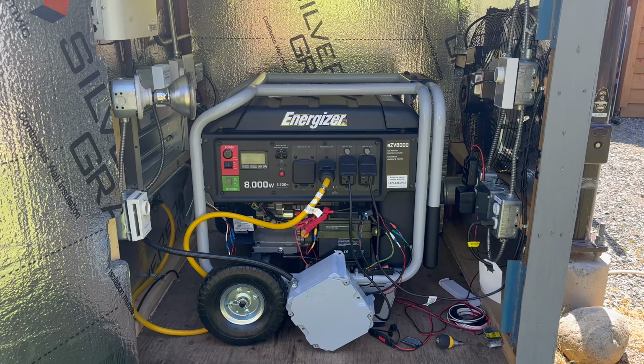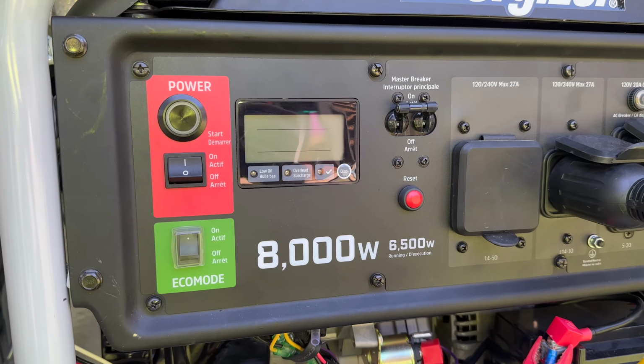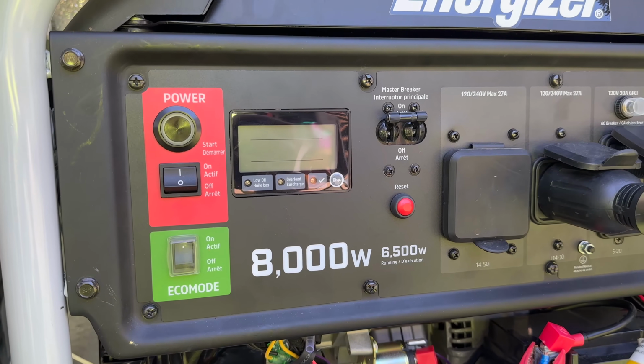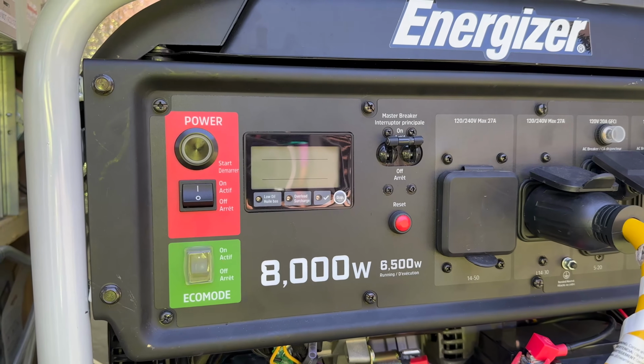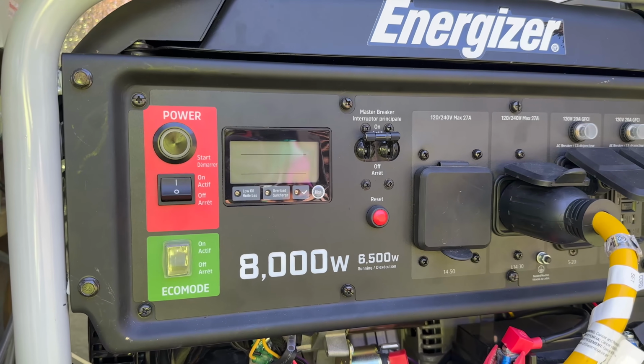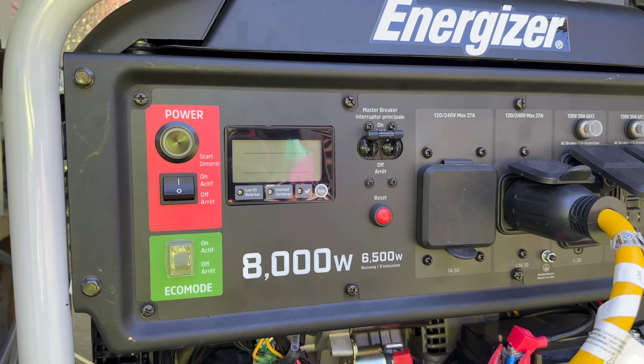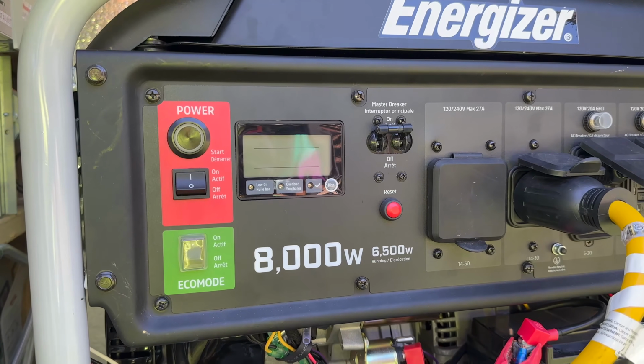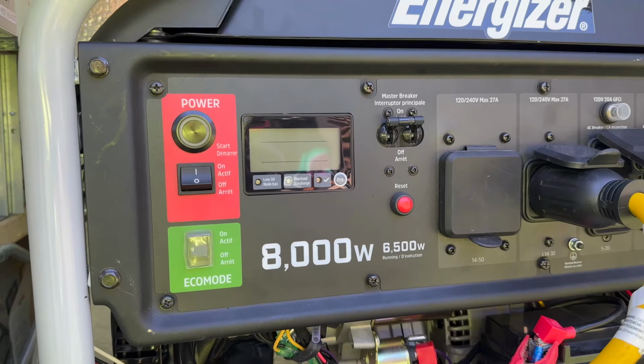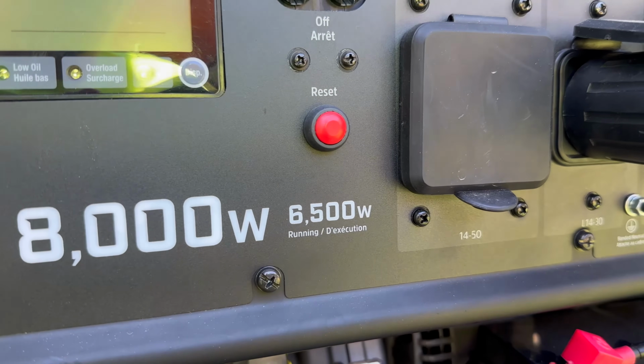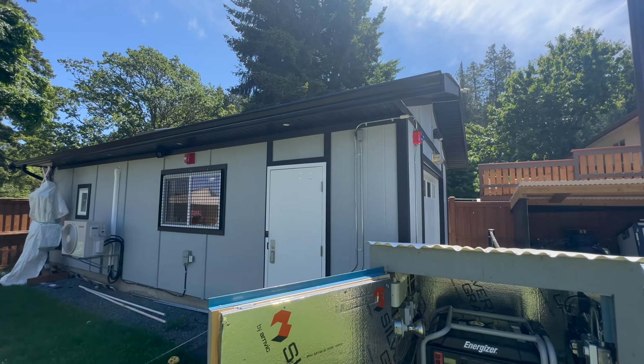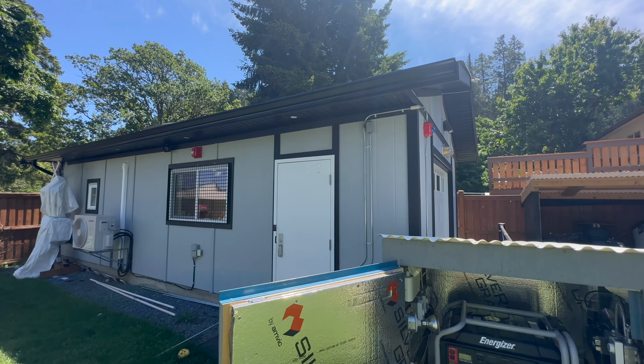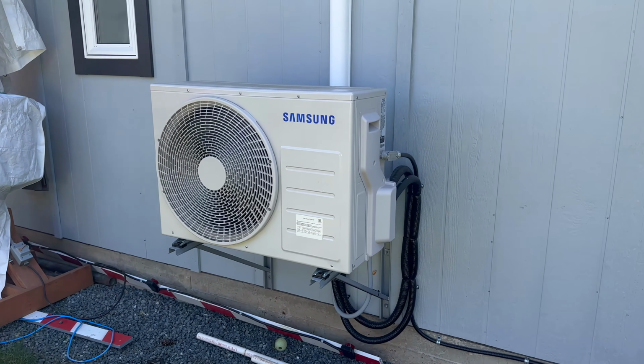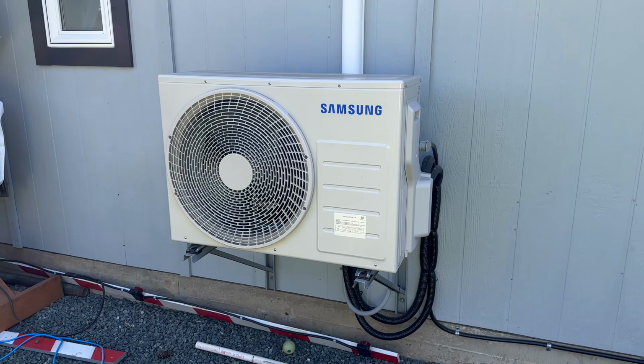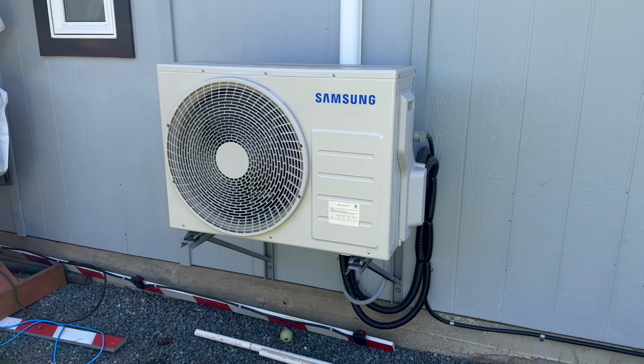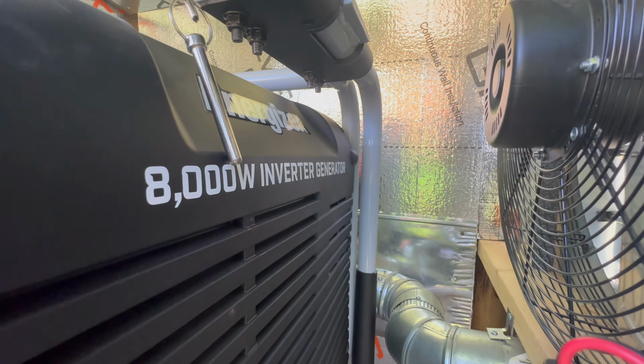For the generator itself, this generator is capable of putting out 8,000 starting watts and 6,500 running watts. The difference is the starting watts are the surge as your power initially comes on, and you have a spike in current from motors and induction type loads that put a large startup current, and then it will sustain 6,500 watts running, which is plenty for this building as it has a very small heating load. As last year I installed this ductless mini split heat pump, which provides cooling and heating and is very low current draw. This, however, is an inverter generator.